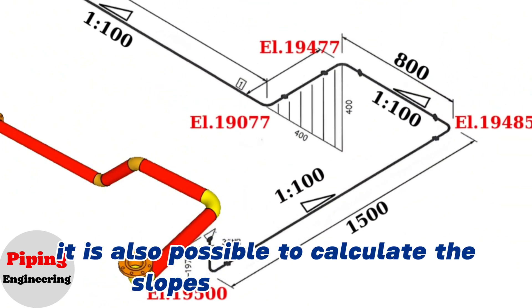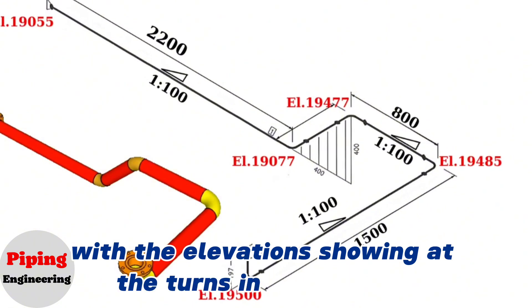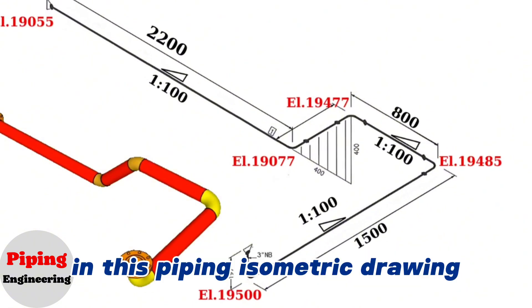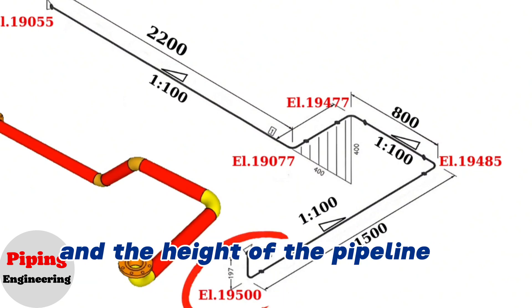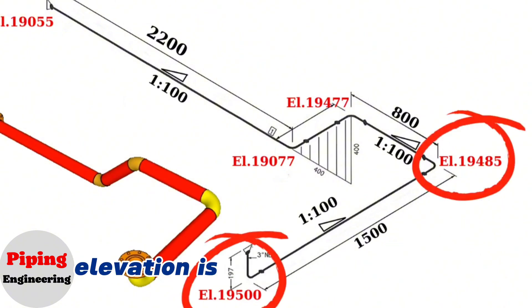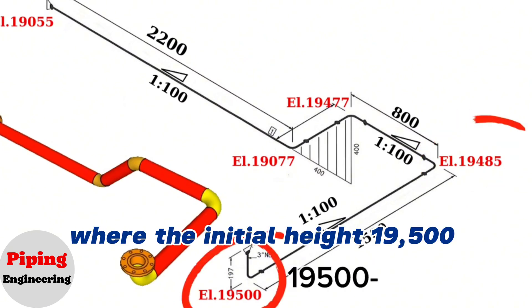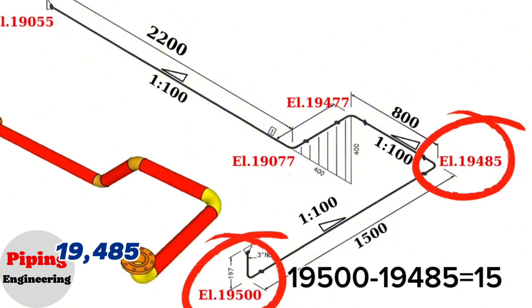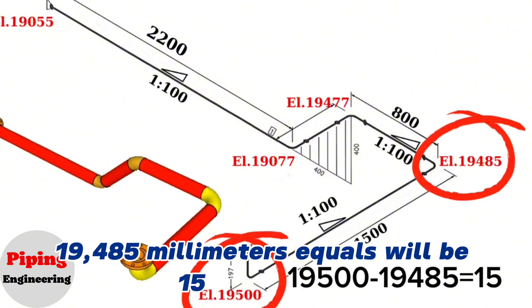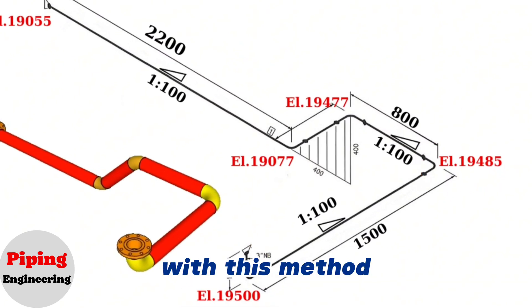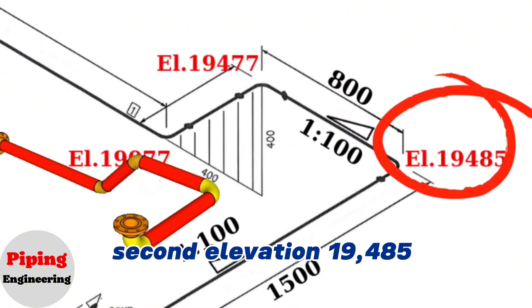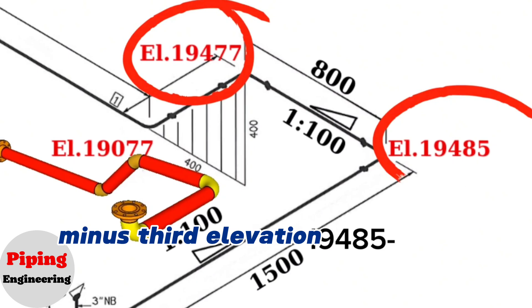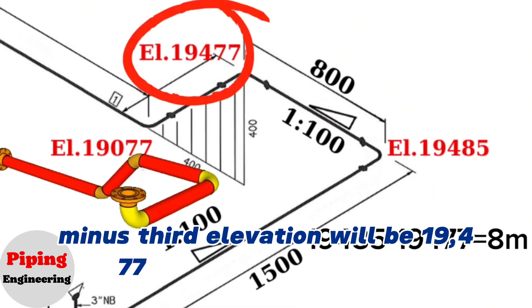It is also possible to calculate the slopes in the pipelines with the elevations showing at the turns in the pipeline. In this piping isometric drawing, the initial height of the pipeline elevation is 19,500 mm, and the height of the pipeline at the second turn with a slope of 1 colon 100 elevation is 19,485 mm. Where the initial height 19,500 mm minus the second height 19,485 mm equals 15 mm. With this method we can calculate the difference of the levels in the second and third rotations. Second elevation 19,485 mm minus third elevation 19,477 mm equals 8 mm.